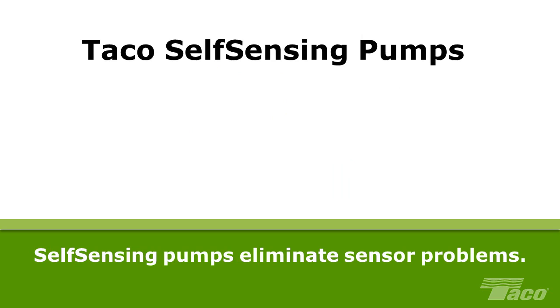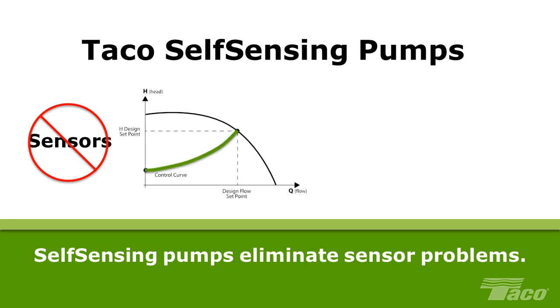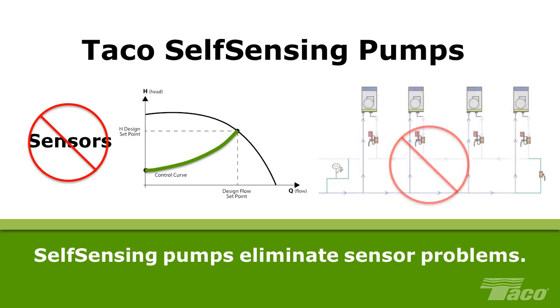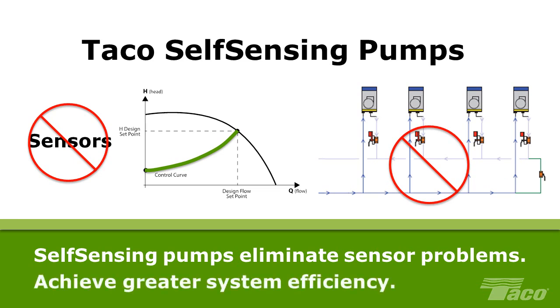In comparison, Taco self-sensing pumps do away with pressure differential sensors and all the problems associated with them. Guided by its control curve, a self-sensing pump maintains the most efficient operating point to meet system requirements at any given time. You no longer have to move sensors to a new, more optimal location in the system. The self-sensing pump enables you to quickly adjust the control head as needed to achieve greater system efficiency.